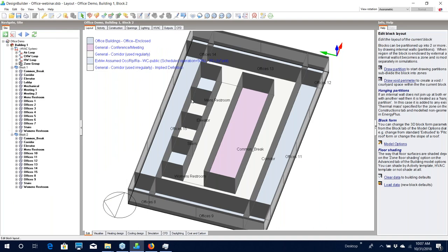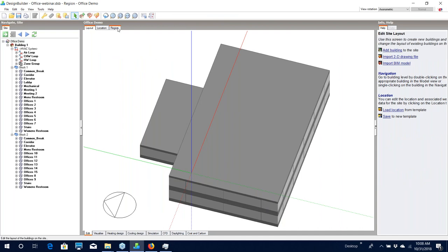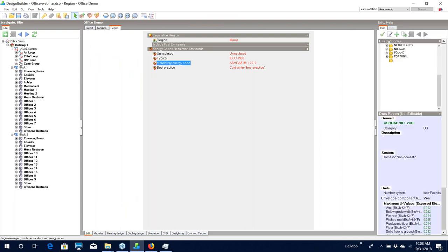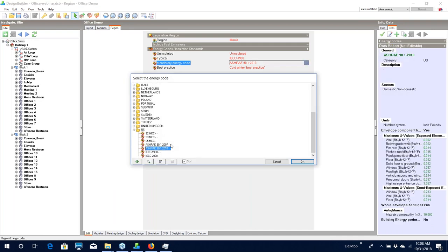Before we create the baseline building we should check a few settings to prepare for the baseline wizard. If we go to site level and look under the Region tab, you can see a setting for the mandatory energy code — this should be set to either ASHRAE 2007 or ASHRAE 2010. Typically you will select this when you add a new building to your project, but it is possible to make this change later, so if you start off with a project that's not an ASHRAE 90.1 building you can come in afterwards, make this change, and then be able to create a baseline building.